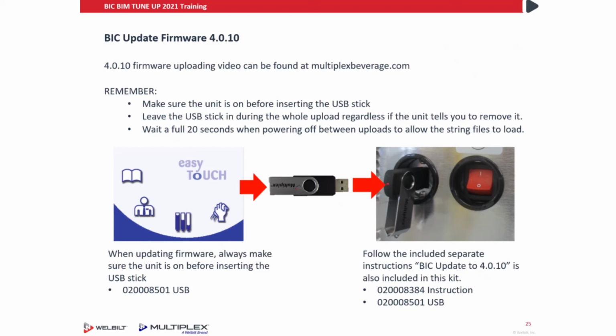Wait a full 20 seconds when powering off between uploads to allow the string files to load. When updating firmware, always make sure that the unit is on before inserting the USB stick, which is part number 020008501 included in your kit. Follow the included separate instructions, BIC update to 4.0.10, which is also included in that kit.